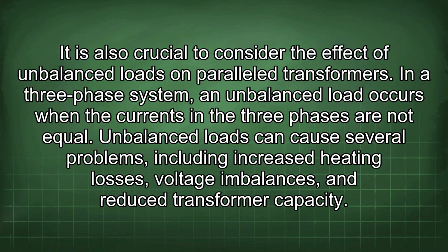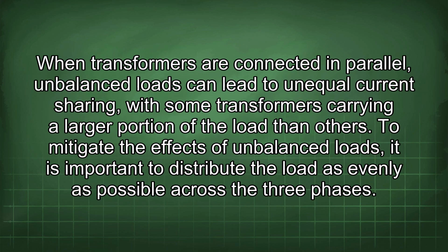It is also crucial to consider the effect of unbalanced loads on parallel transformers. In a 3-phase system, an unbalanced load occurs when the currents in the 3 phases are not equal. Unbalanced loads can cause several problems, including increased heating losses, voltage imbalances, and reduced transformer capacity. When transformers are connected in parallel, unbalanced loads can lead to unequal current sharing, with some transformers carrying a larger portion of the load than others.